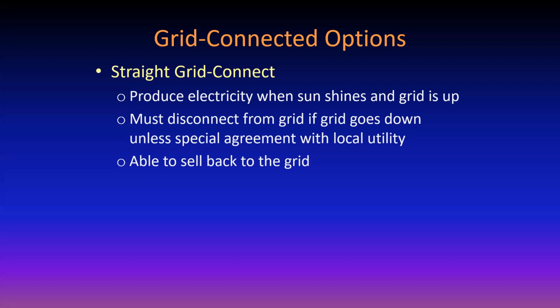And we'll talk a little more about the rules there. That's UL 1741. And the nice thing about grid-connected photovoltaic systems is that if they're making more electricity than is needed by the occupancy, the remainder gets sold back to the grid, typically at the same rate at which the owner is paying the utility for the electricity. That's still generally a pretty good deal for the utility, because when this PV electricity is being made during peak time for the utility, it generally costs the utility a whole lot more to make electricity during their peaking time than what they would end up buying it back for from an owner of a photovoltaic system. So that's a straight grid connect: no storage, no backup, and if the grid goes down, the system goes down.